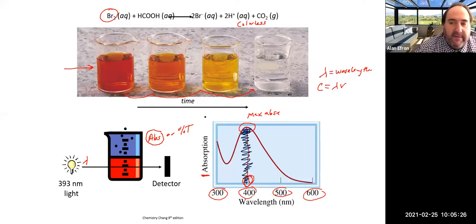So what would happen if you decided, hey, I'm going to set the machine to a wavelength in this region? Well, that means you only have the ability to measure absorbance about that much, which means in this particular example, most of your samples probably wouldn't give you a value. You'd get a lot of error messages and stuff like that. So it's important to know the proper wavelength to set a machine such as this to.